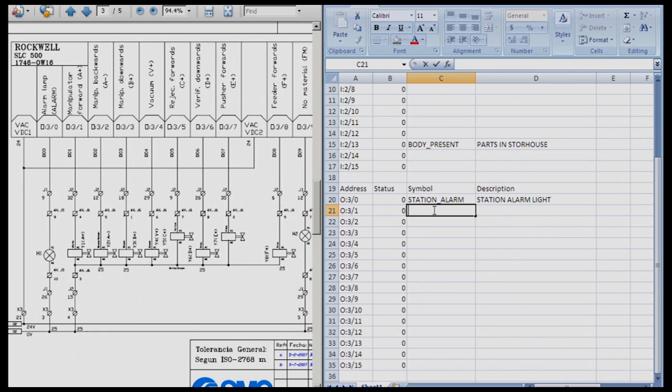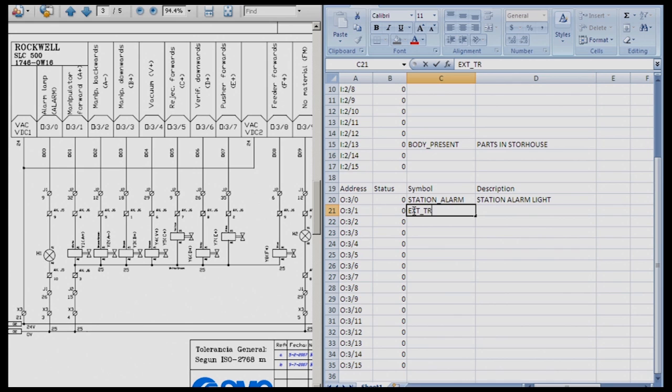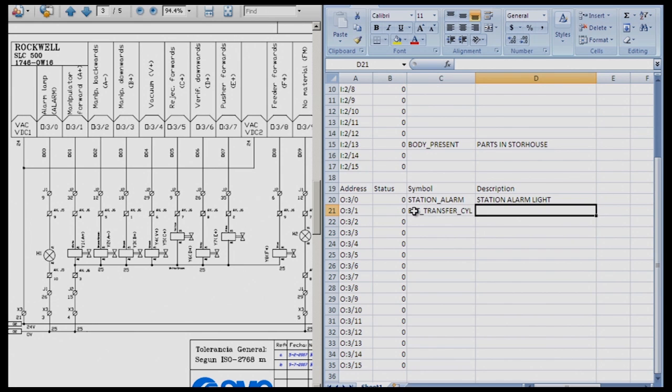So our next output, O colon 3 1, which is manipulator forward. Now, this is where it must match what you called your inputs. So I did not like manipulator forward. I changed mine to transfer cylinder. So it needs to match that. So I'm going to call this extend EXT underscore transfer underscore cylinder. That is my symbol. So that means I'm going to extend the transfer cylinder. So when output O colon 3 1 is on, we can expect motion to happen.